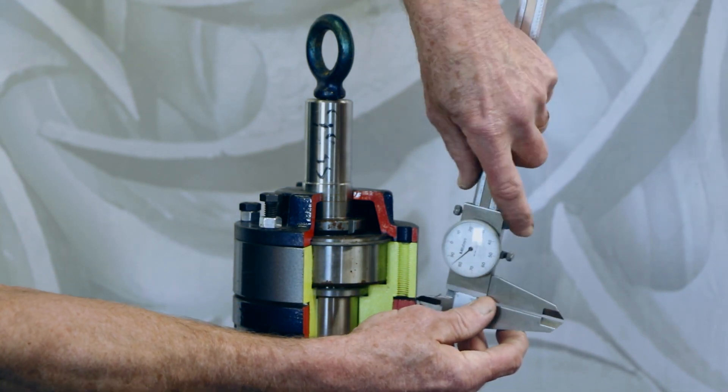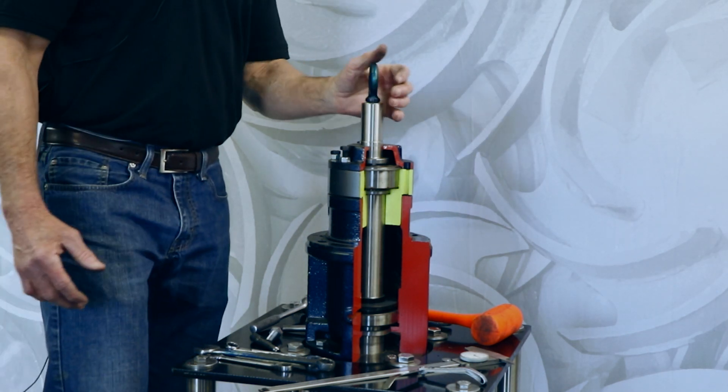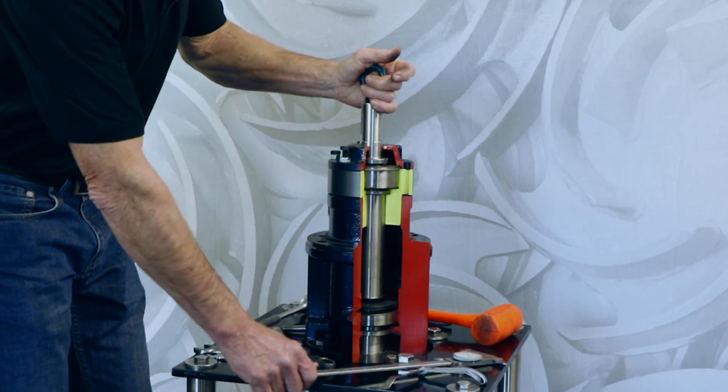We would like no more than three thousandths, and it's especially important when you're running a high-speed pump, because the bearing will heat up, the shaft might break. So we definitely suggest you do that.